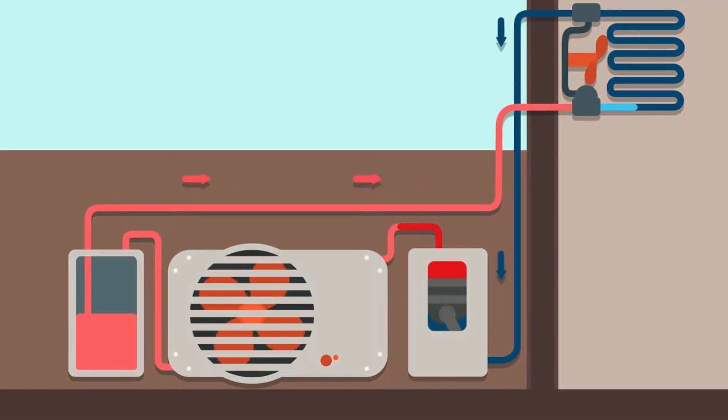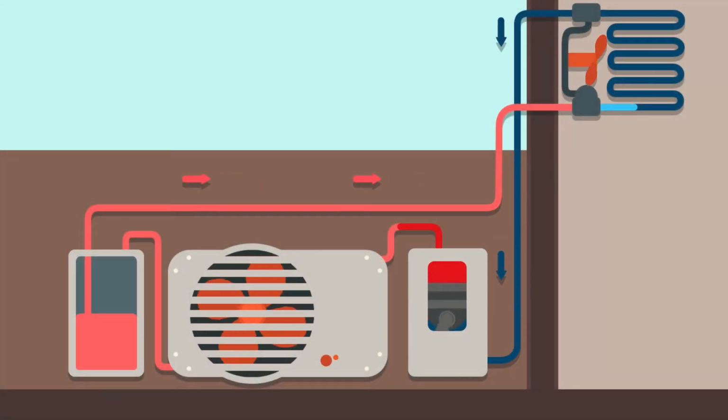In the refrigeration cycle process, there are 4 elements. Starting from a compressor, the refrigerant gas is compressed into a hot, high-pressure gas. Right after the gas gets hot, it goes to the condenser where it will be cooled. As the refrigerant cools, it condenses into a liquid state. The liquid is cooled by surrounding the pipe containing the refrigerant with cold water or air.